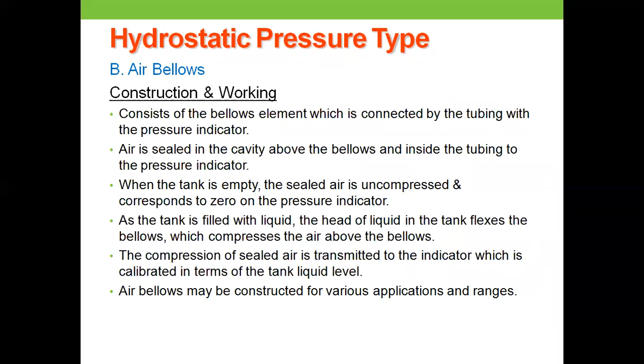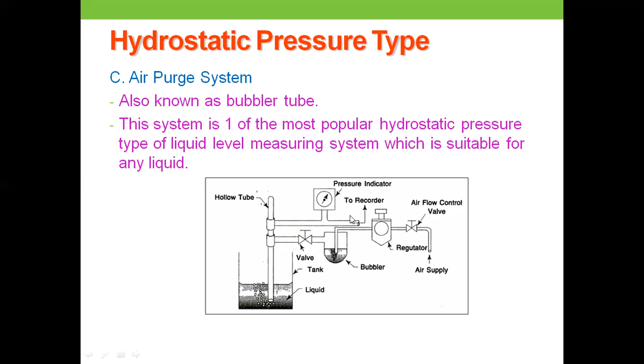Next one is the air purge system. It is also known as the bubbler system. Hydrostatic pressure in different types of liquid level measurements is very suitable for measuring these characteristics. So in the bubbler system, a hollow tube is maintained, as the diagram is showing here. From this hollow tube, the air is circulated, and upon expansion, the air that has been supplied internally into the liquid escapes, and the bubbles burst at the surface level, and that level is indicated at the pressure indication recorders.